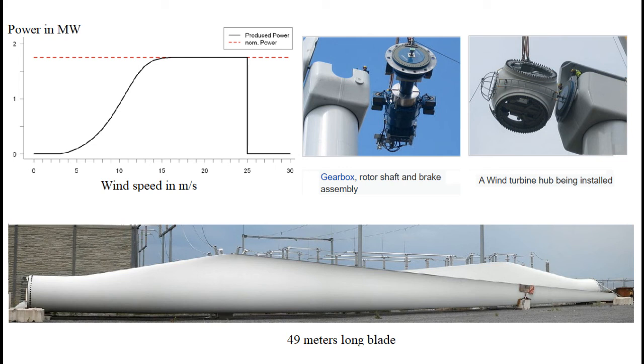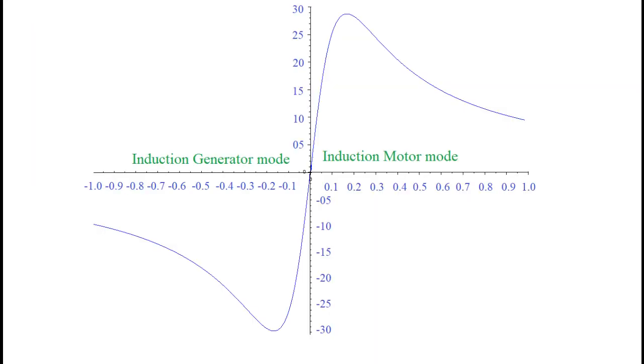The complete grid system tries to pull a lagging or leading machine into synchronism, but this forcing of the alternator into synchronism also has some limitations. If speed is crossing the limit of stability, then the system could not remain in synchronism. Another option is an induction generator. This generator does not need exactly synchronous speed. Induction generator works in a comparatively wide range of speed and torque.